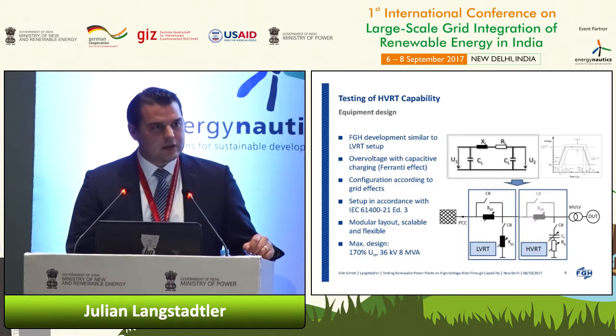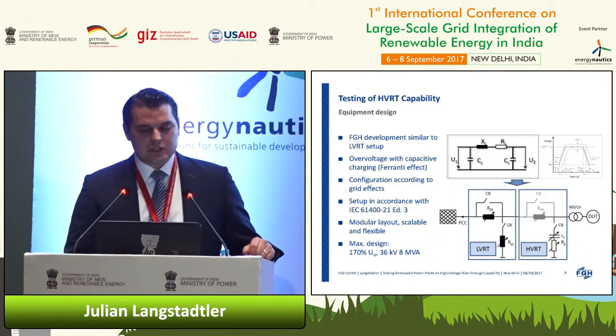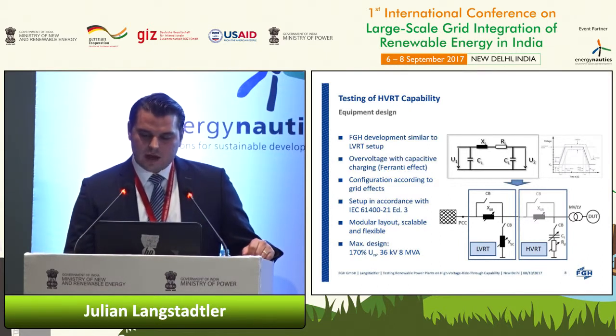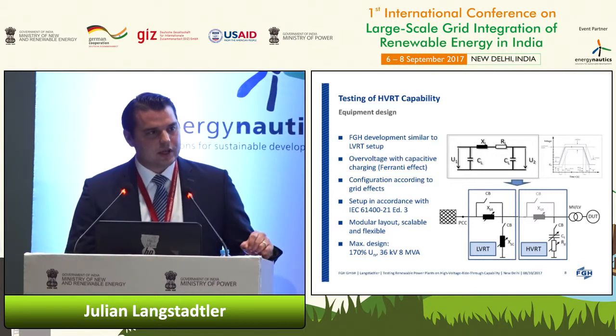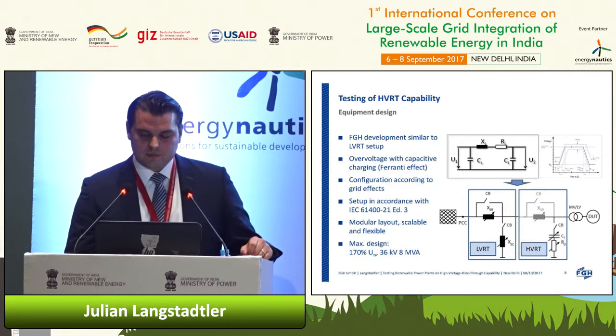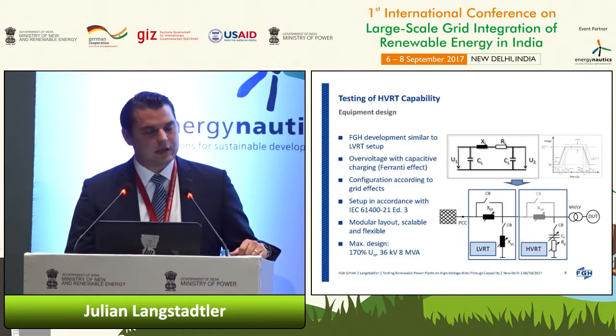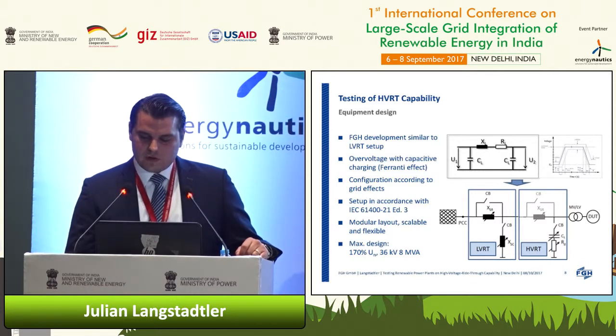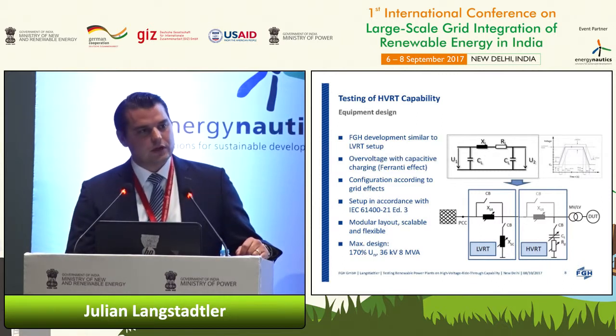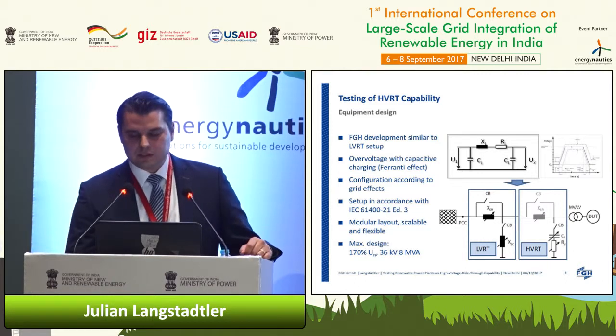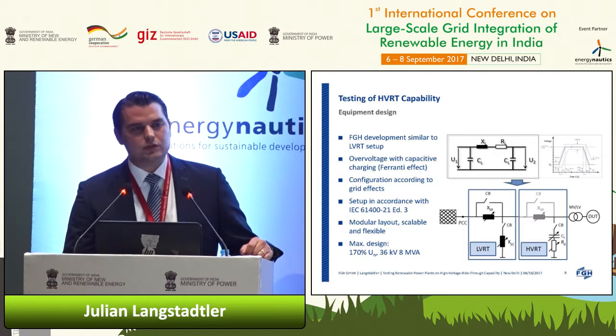However, if there is an unloaded transmission line, at the end you have only the vertical path, which affects the voltage itself, so mainly only the capacitor has an impact. This is also shown in the HVRT setup system, where the short circuit with the inductance is simply replaced by a capacitor with a damping resistance. So actually the serial impedance is still the same, and you can use it redundantly.